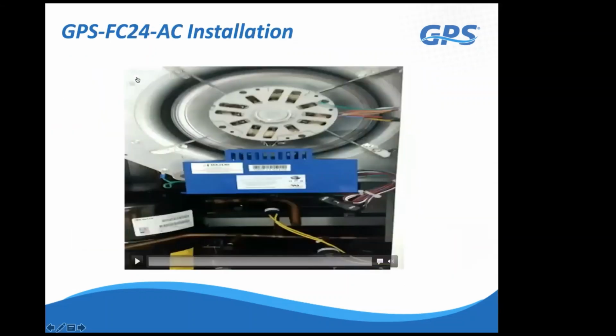Here's what it looks like installed to a fan inlet. This could be fan coils, heat pumps, small air handlers, could be even VAV boxes if you're trying to treat specific zones off of a larger air handling system, or fan powered boxes. Those are good applications for this device. It's also only 1 inch in depth, so it fits well in your ceiling cassette units. If you've got like the 2-way or the 4-way ceiling cassette units, just take down the return grill and the filter, and this fits nice between the filter and the fan inlet.